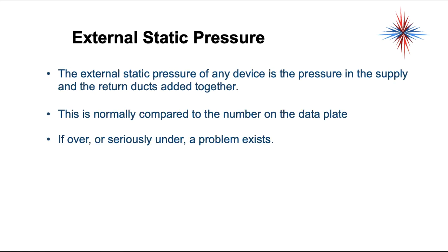Total external static pressure of any device is the pressure in the supply and return ducts added together. In your supply duct you have a positive pressure; in your return duct you have a negative pressure. Take the absolute value — drop the signs — and add the two numbers together. This total external static pressure is compared to the number on the data plate. If it's over or seriously under, a problem exists.